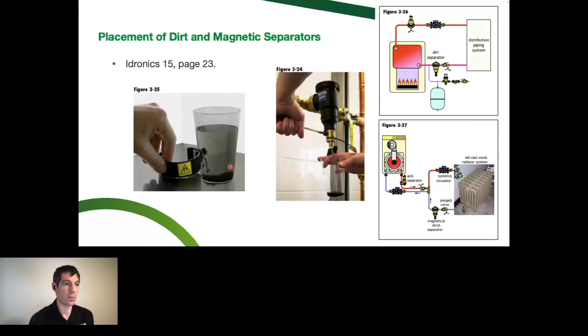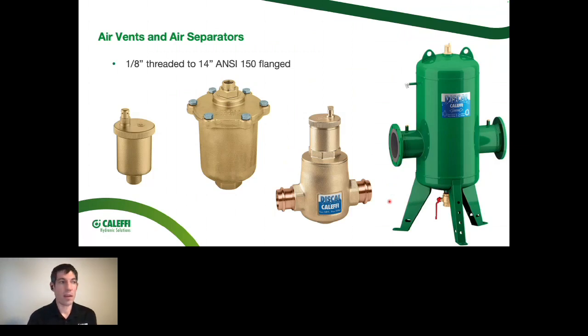The test, there's no specific rule there. In a system like this with old cast iron radiators, you're just going to do that forever. You're going to have some sort of air that's going to enter the system in the building. You're always going to be kind of rusting from the inside out. Or if there's a leak and you're introducing fresh oxygenated water through an autofill valve or something like that, the game keeps going on and on and on, and you have to catch that magnetite and keep up with it over the years.